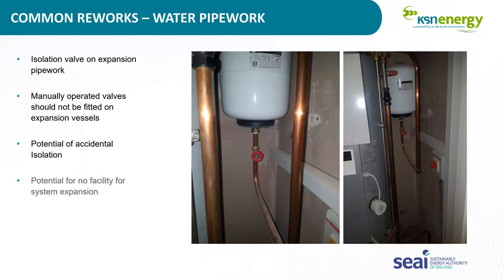The next one here, I get the purpose of why an installer does this. It's putting an isolation valve on an expansion vessel. And as everyone knows, when you heat water, it expands. That expansion has to be taken up somewhere, and an expansion vessel is installed to take that up.